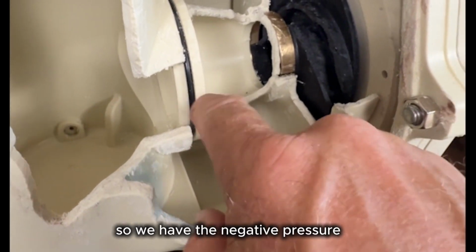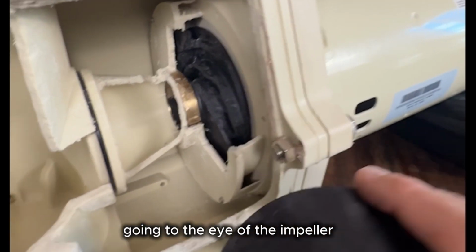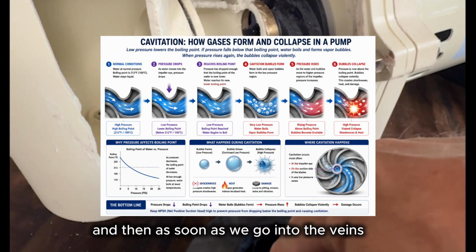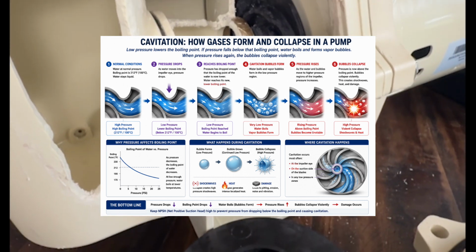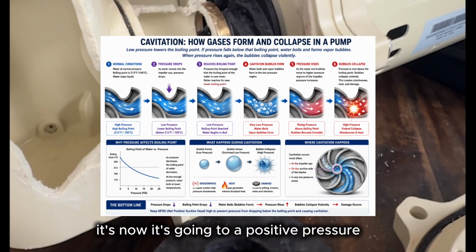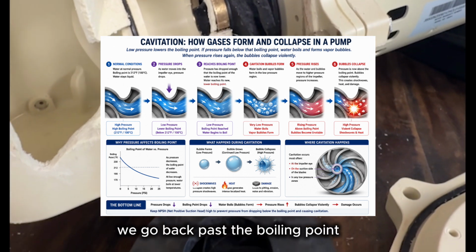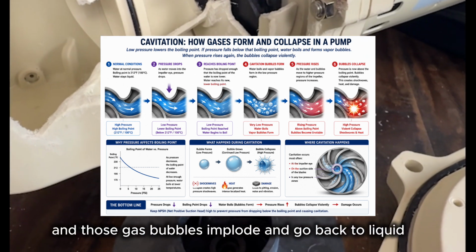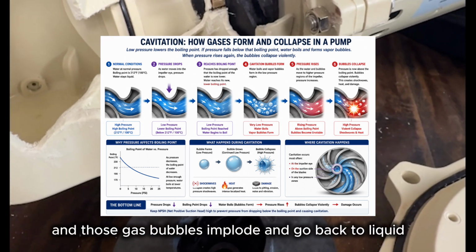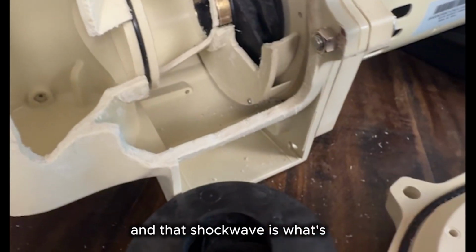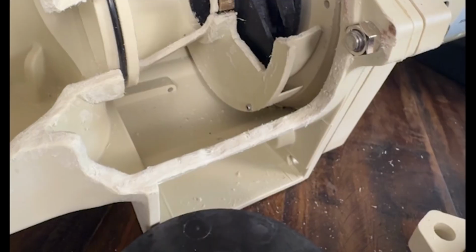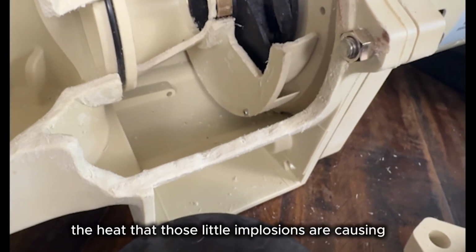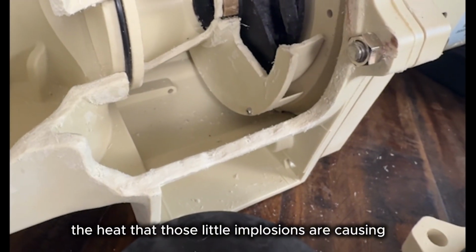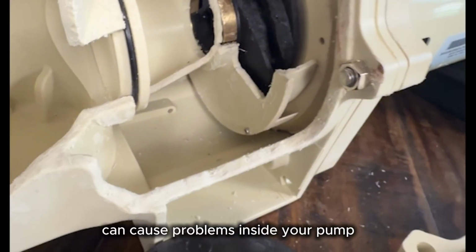So we have the negative pressure going to the eye of the impeller, and then as soon as we go into the vanes, it's going to a positive pressure. We go back past the boiling point, and those gas bubbles implode and go back to liquid, and that shock wave is what's causing problems. That shock wave, as well as the heat that those little implosions are causing, can cause problems inside your pump.